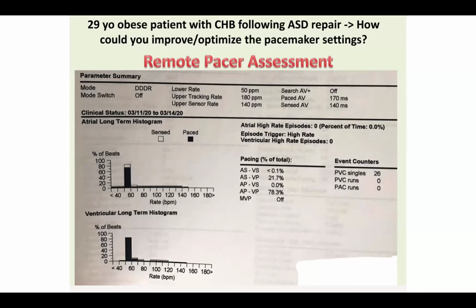But interestingly, you would think that someone who is paced 78% of the time when their lower rate limit is set at 50 almost certainly does have sinus node dysfunction. So I would argue that based on what we're seeing here, it was probably the right idea to put the rate responsive feature on to get a more physiologic heart rate. But it is unusual. It's actually interesting, right? If we look at the percentage of beats that are paced versus sensed, we see that still the vast majority of his pacing is less than 60 beats per minute, despite the fact that the rate responsive feature is on. So even with rate responsiveness on, he really isn't pacing in the atrium much above 60. If you add all of this together, it's probably 10% of all his pacing that is above 60.